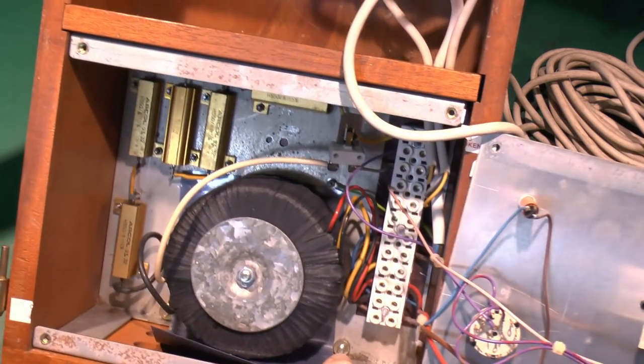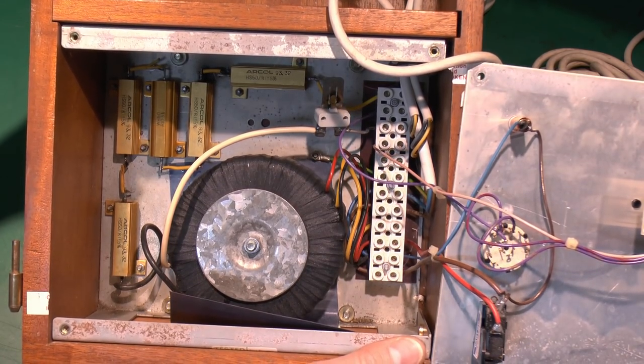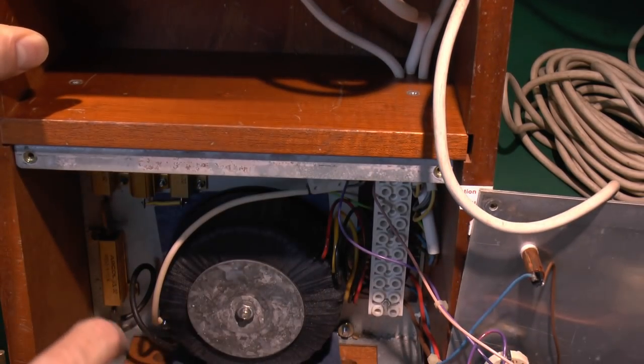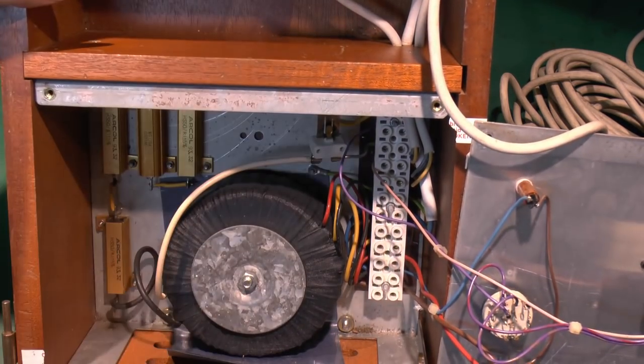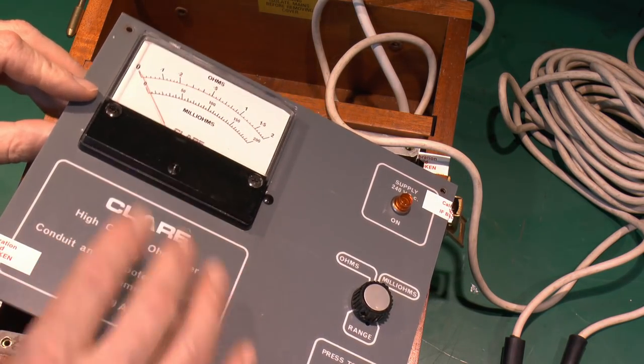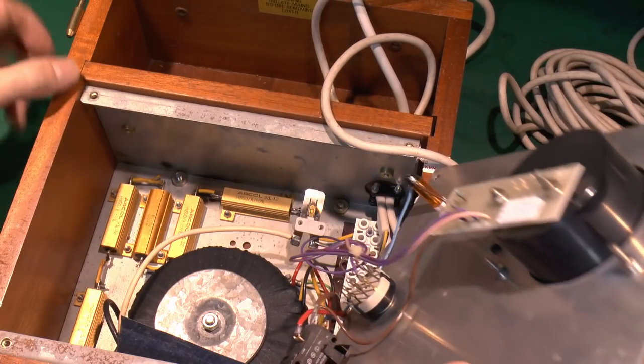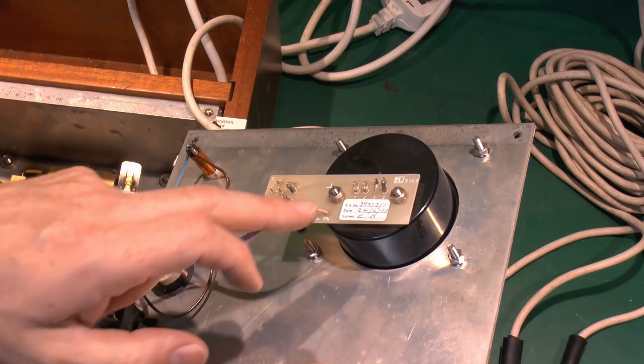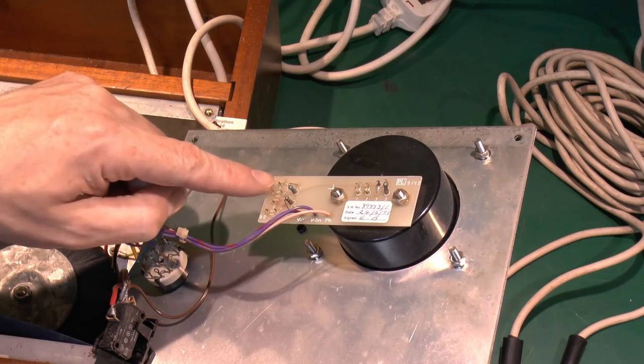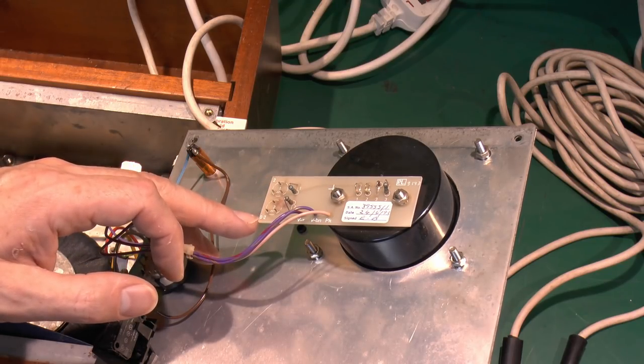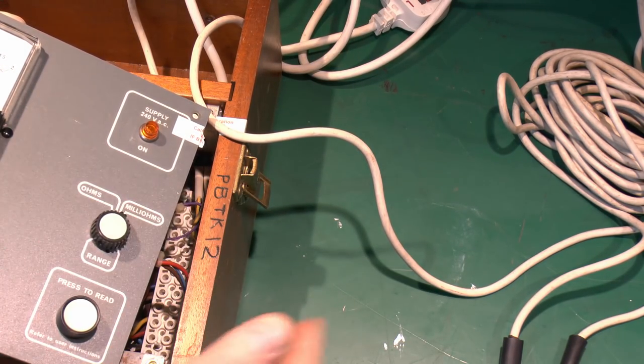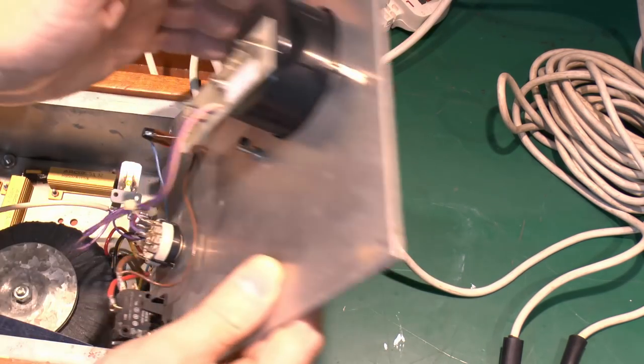So there's just a view of the entire thing again. There's a cable grip at the top here, and then the three wires just come through the holes on the back here, and they do actually have their own individual holes drilled through. Fairly decent design, and that's just a storage compartment there for where they are when this thing is being transported. And then the only other thing to note here really is this meter here, which is obviously the output reading there. You can see the back of it here. We've just got on the back the two terminals which connect to the meter. A small circuit board with a few resistors and things on there. And then here we've got two variable resistors on this end, and they're actually on the underside of the board. And this is presumably where you would set the actual calibration of the meter itself. So the option is to short these together and set it to zero, or apply a known resistance and set it to obviously the correct value. So it does have the facility for adjustment, and I have marked it here as 2 and 0.2, so it's going to be one for each of the two scales.